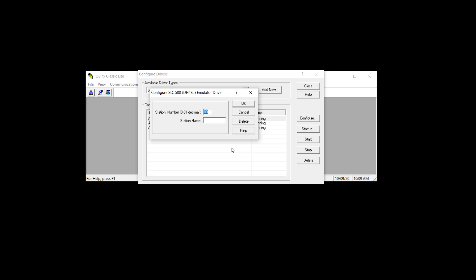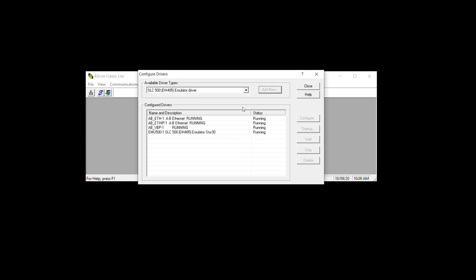Now we're not going to do that. Also keep in mind that RSLinx is a driver manager and this particular driver is kind of an odd man out in that it doesn't connect between the programming platform and a serial port on your computer. It's a software loopback. So it actually in a sense goes towards a port and then loops back to another location in RAM. Just like with a Micro 800 simulator, it has a software loopback Ethernet address that you can use. In this case we're doing a DH485 and our computer is going to be 0 and then our controller is something else. Click OK and there you have a driver running.